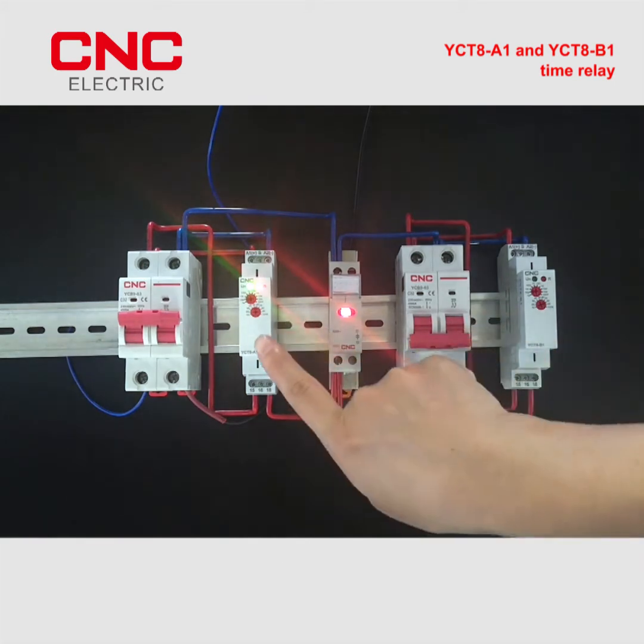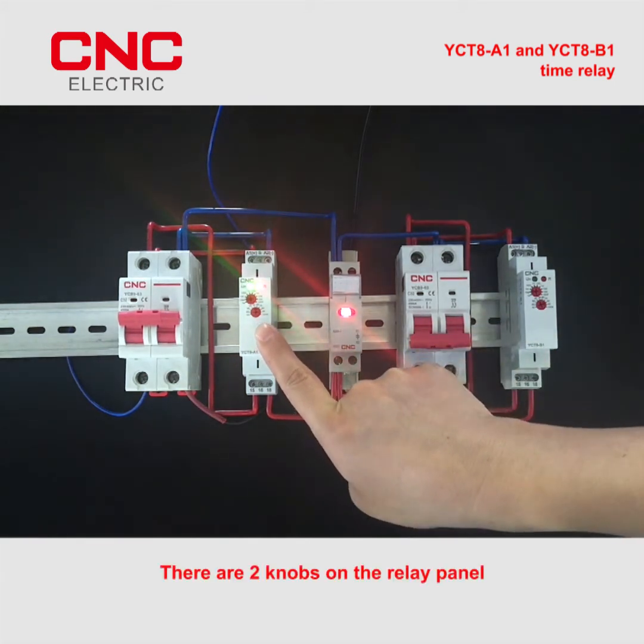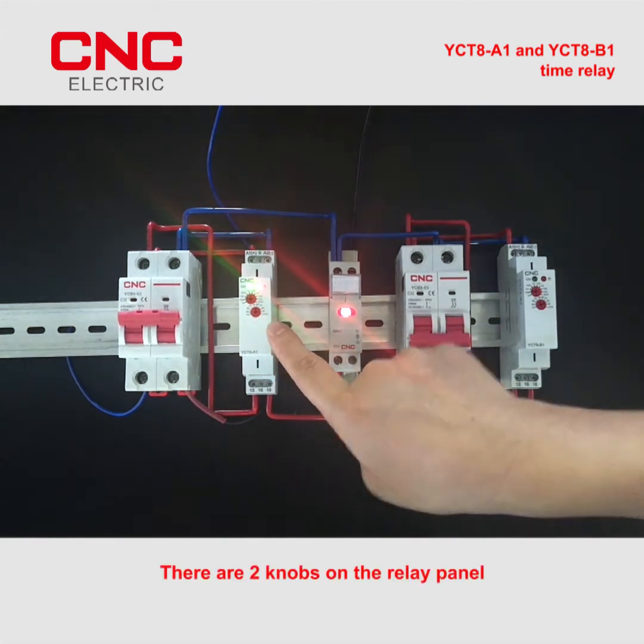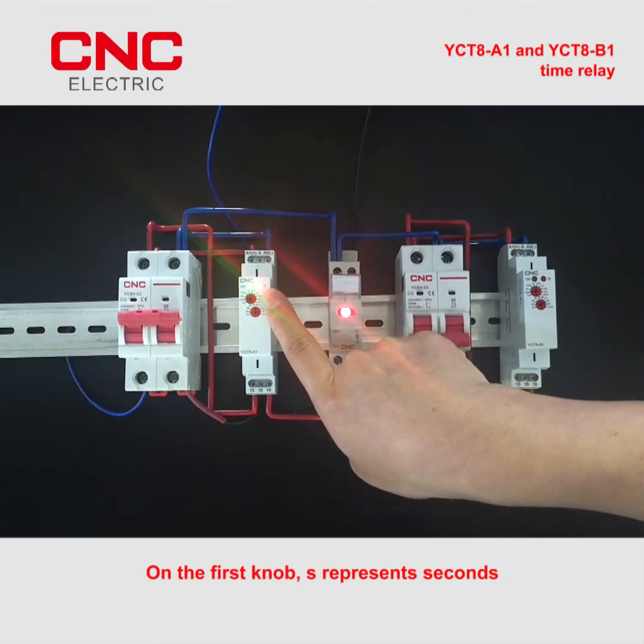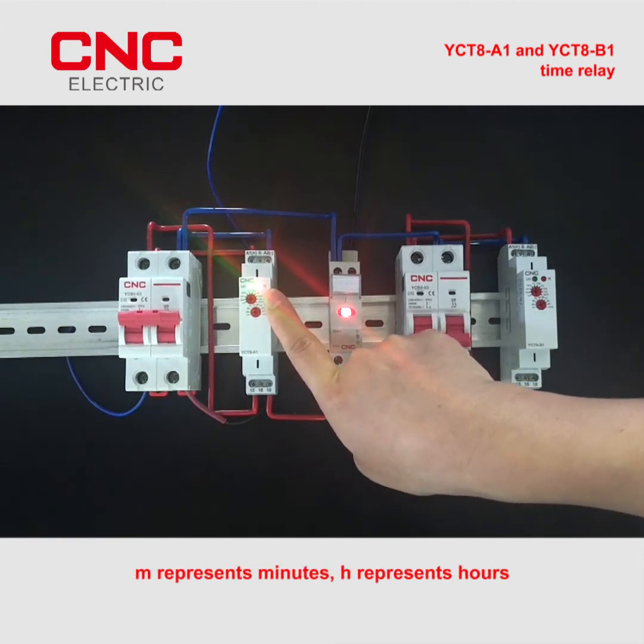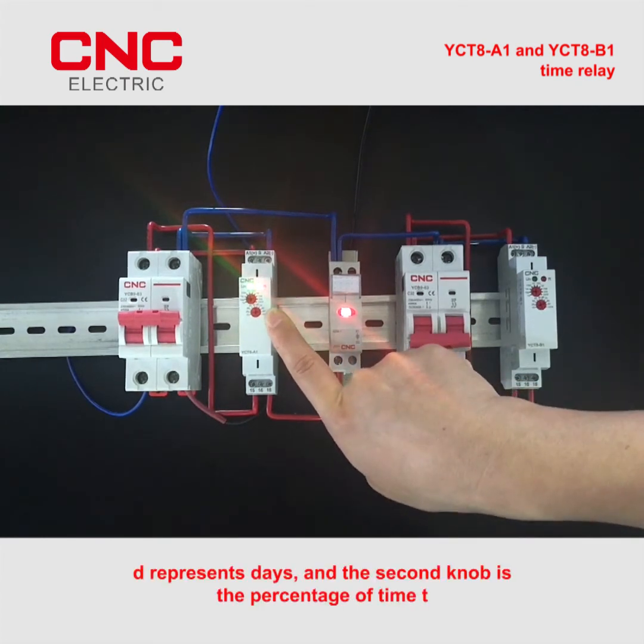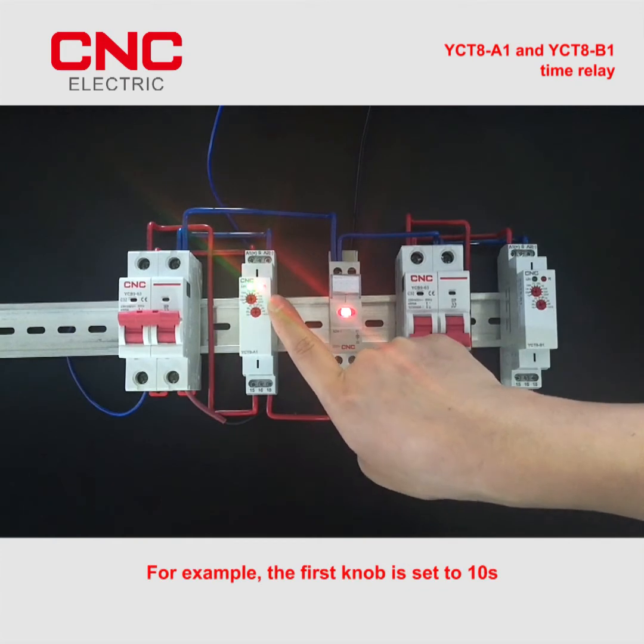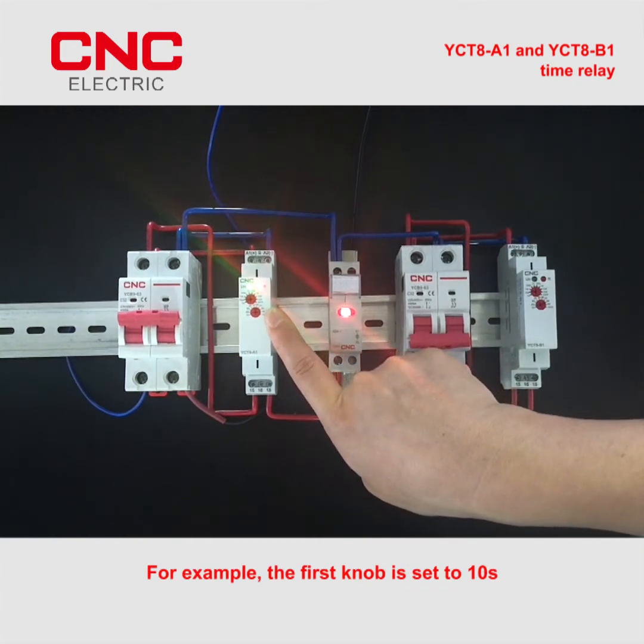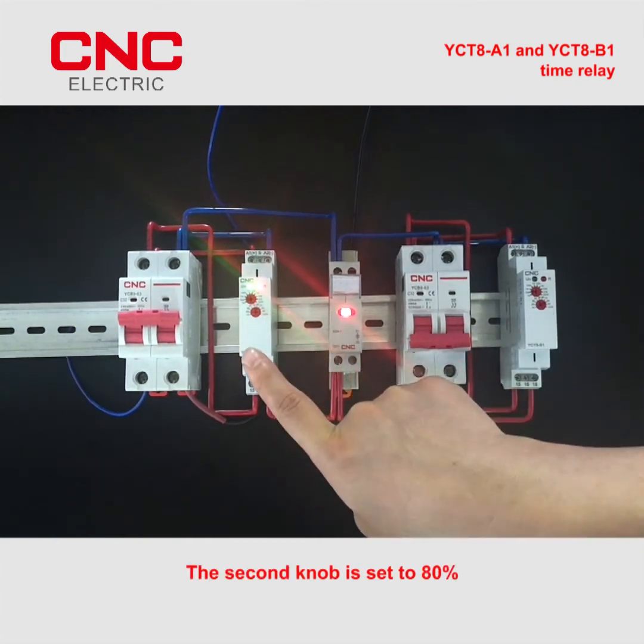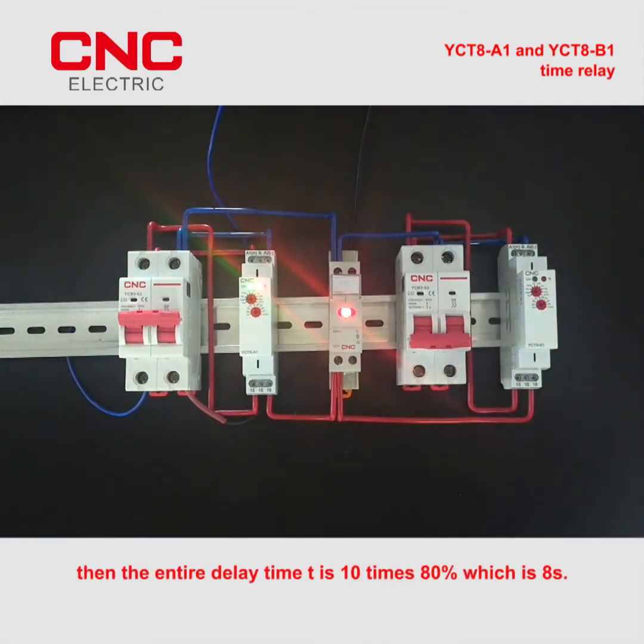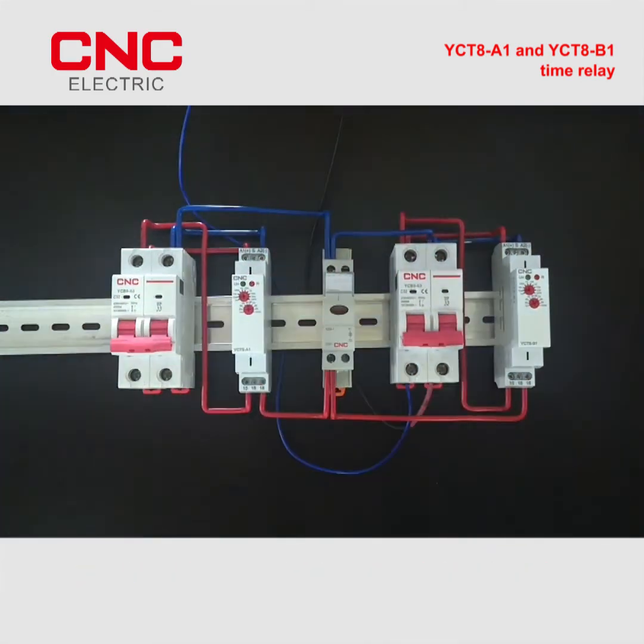Time setting. There are 2 knobs on the relay panel. On the first knob, S represents seconds, M represents minutes, H represents hours, D represents days, and the second knob is the percentage of time T. For example, the first knob is set to 10s, the second knob is set to 80%. Then the entire delay time T is 10 times 80%, which is 8s.